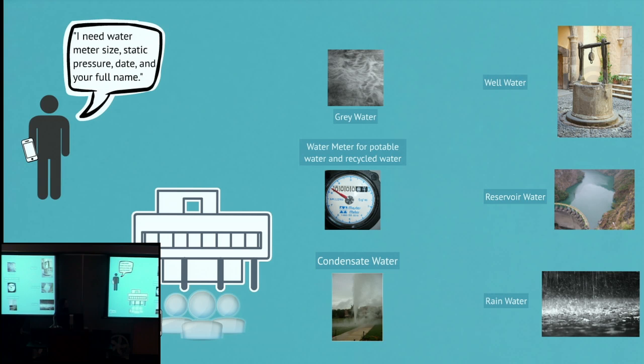So if you see, this is supposed to be the water agency building. So you would call them, get your water pressure, and static water pressure and the meter size. And again, up here, make sure you get their full name and the date. Believe me, many times that saves us when we can't look at the water meter out in the field and find out it's a 1 inch rather than a 2 inch. Okay, so this is an actual water meter right here, and then just pictures of other types of water source.